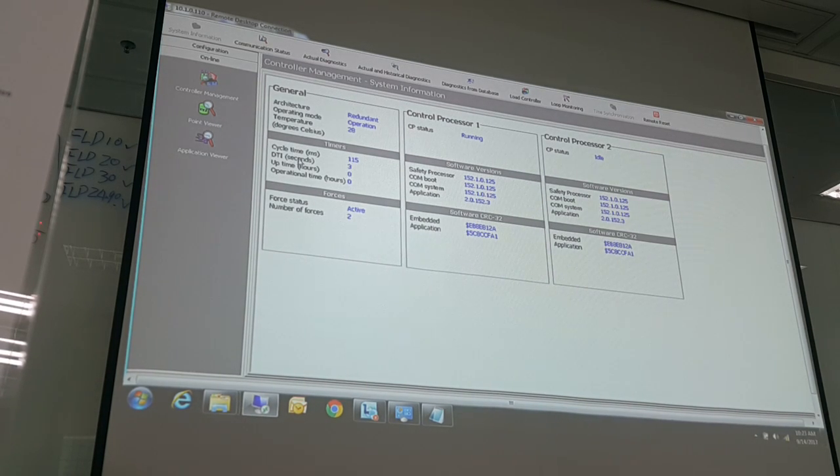And you can see this is 3,000 milliseconds, right? And this is only 115 milliseconds. So it is shorter than this DTI. So our system is very healthy.